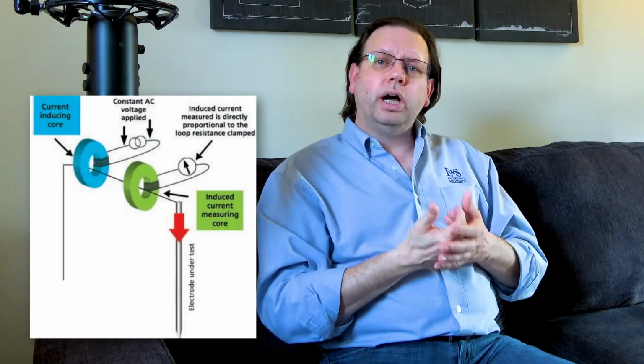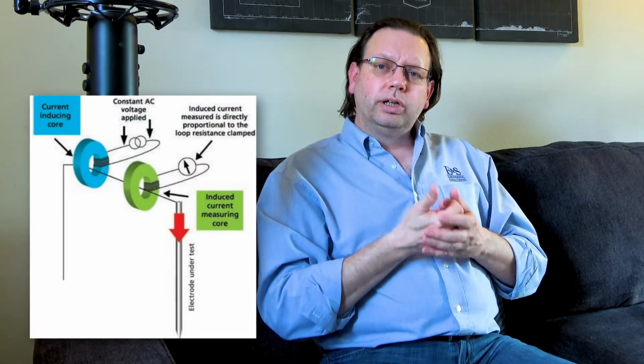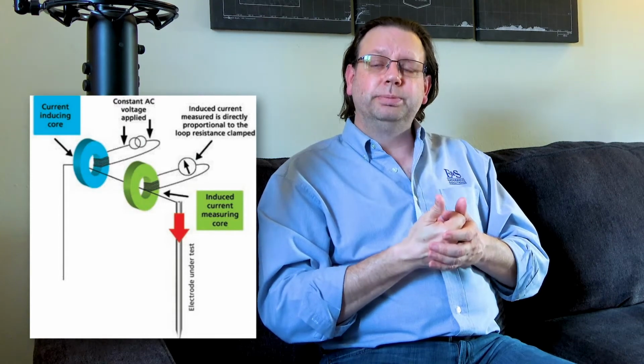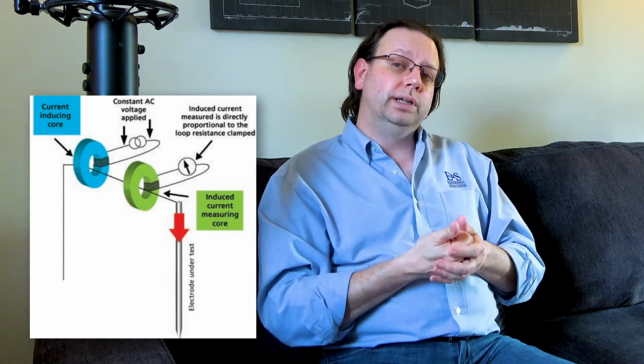And you can almost envision that as kind of like this long distance check across. We were talking about a 100-foot by 100-foot substation, and we found the master ground bar inside of the blockhouse. We had these kind of long distance measurements from the blockhouse all the way out to the far corner and all the way back through this massive network. Well, in this case, we're going to take our continuity meter, our clamp-on ground resistance meter, and we're going to use it for continuity in this case.